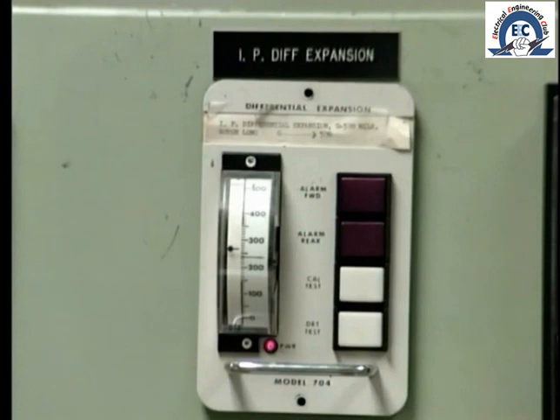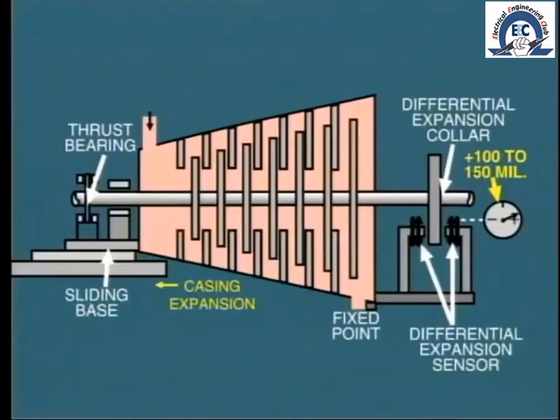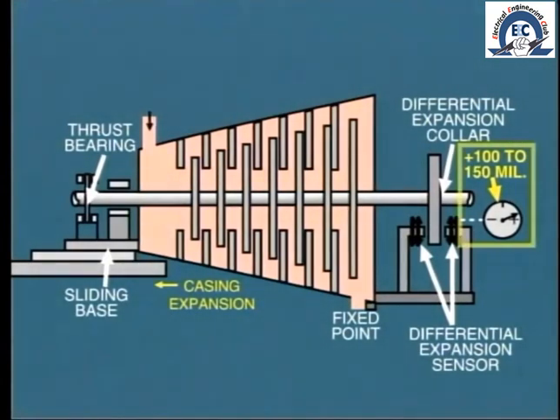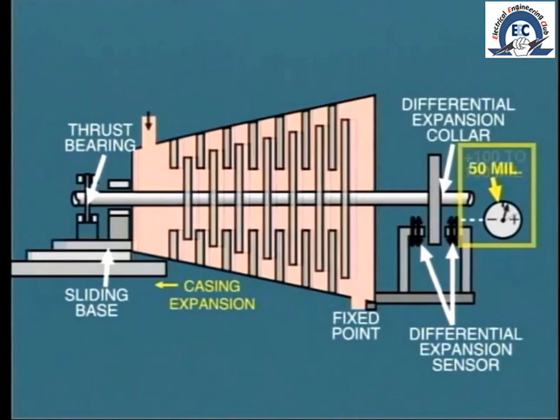Differential expansion is measured and indicated at the operator's control panel or console. Typically during startup, we will observe a positive differential expansion increasing continuously up to about 100 or 150 mil. We may have to restrict loading in order to keep from exceeding this level. Eventually, as the casing expands further and further, the differential will decrease and probably settle down to say, plus 50 mil.